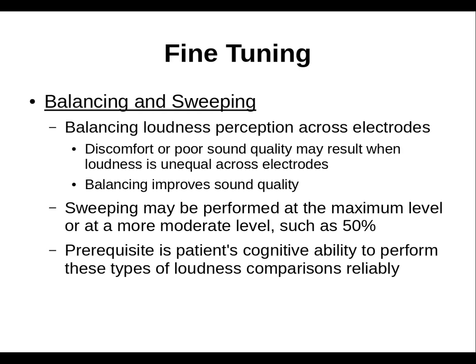Maybe you might have 22 electrodes, and not all of them may be active. Maybe you've got 12 or 15 electrodes active. And each electrode is going to be responsible for, or associated with, a certain frequency range.